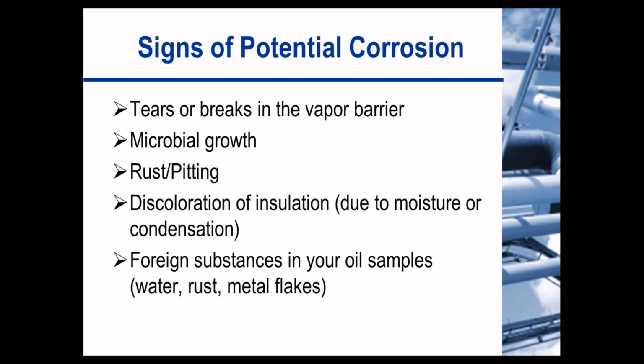So let's review a few things about corrosion. Tears or breaks in the vapor barrier are highly probable places where corrosion may occur. Also look at places where you see microbial growth. Any rusting or pitting is definitely a sign of corrosion. Discoloration of the insulation, due to moisture or condensation, is a likely candidate. Finding any foreign substances in your oil, like water, rust, or metal flakes, is also a sign that you're probably going to have corrosion issues as well.